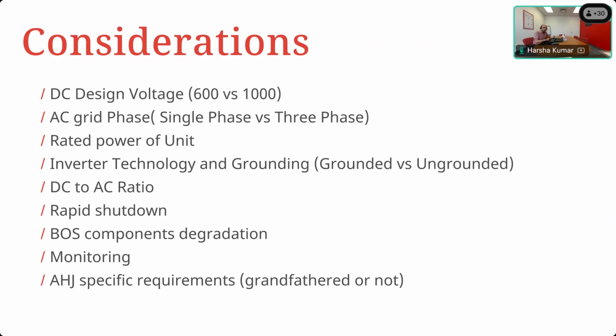Transformer-less inverters are floating inverters. You can have zero contact to ground on the DC side. So neither the positive nor the negative can ever come in contact with ground. If it did, you will lose the inverter. So that is what we call a ground fault.